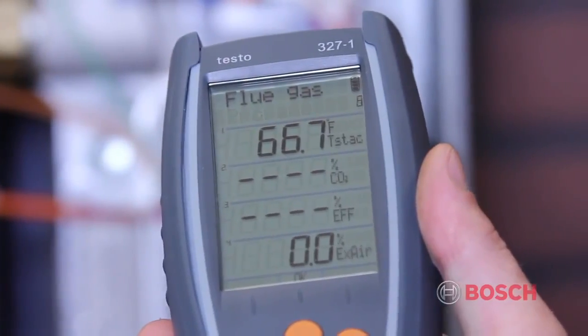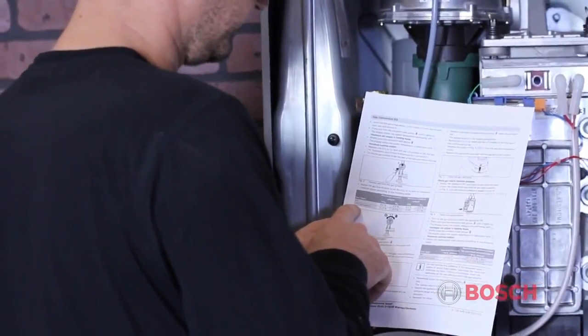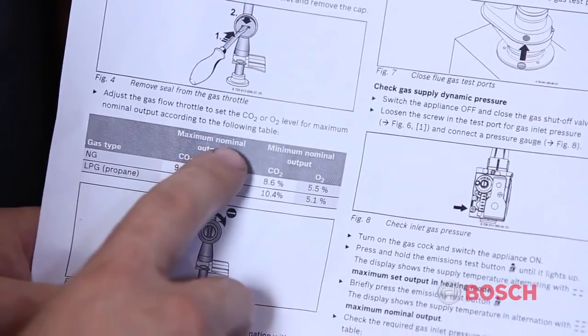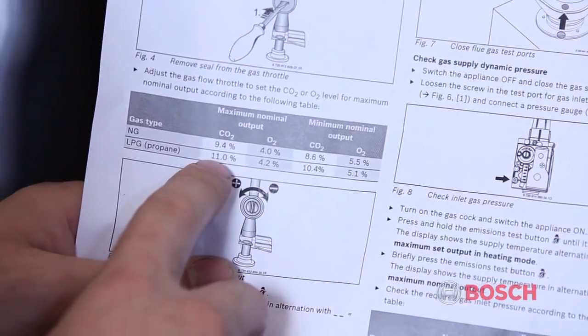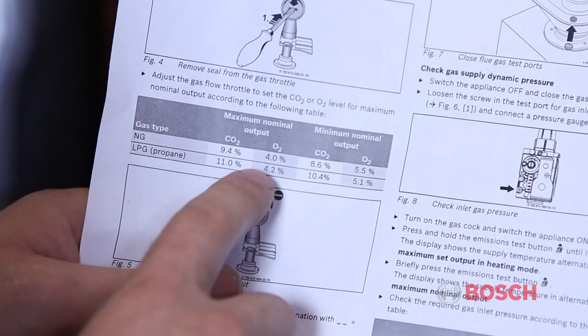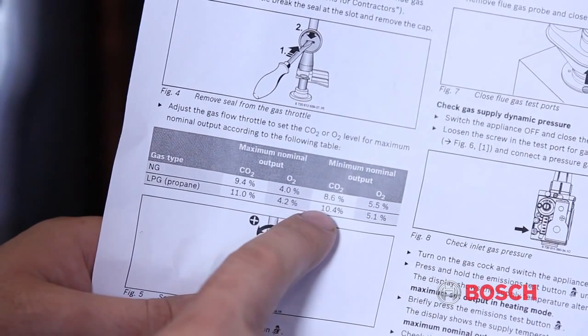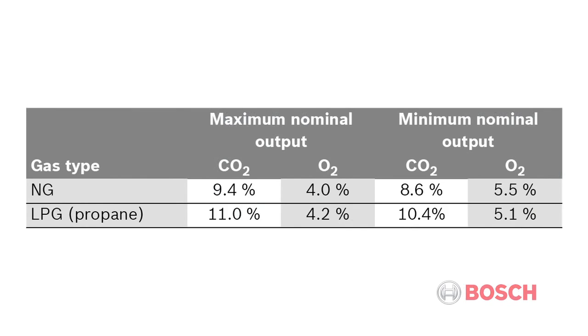Prepare your digital combustion analyzer according to the manufacturer's instructions. Verify that it's set up for the proper fuel. In this example, we're testing for propane. For propane, at maximum output, CO2 should be at 11%, and oxygen is 4.2%. At minimum nominal output, CO2 should be at 10.4%, and oxygen at 5.1%. For natural gas, at maximum nominal output, CO2 should be at 9.4% and oxygen at 4.0%. At minimum output, CO2 levels should be at 8.6% and oxygen at 5.5%.